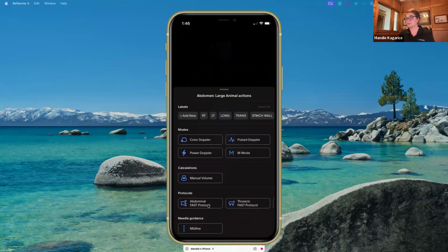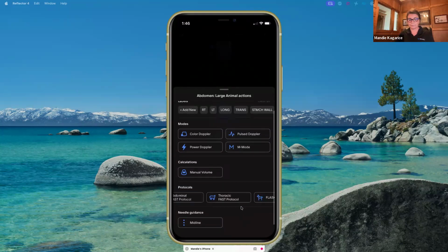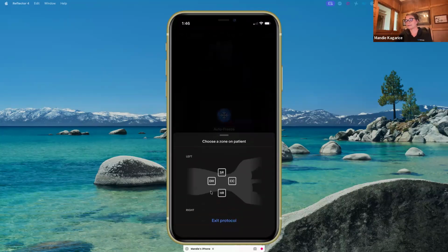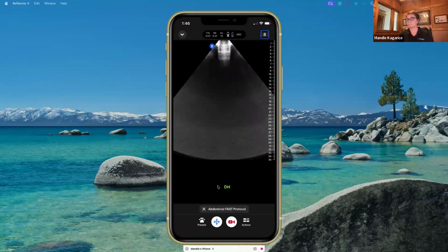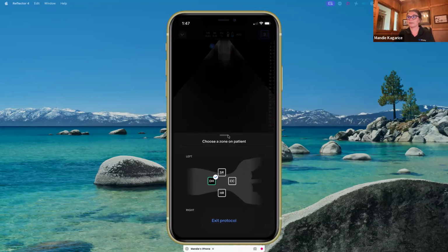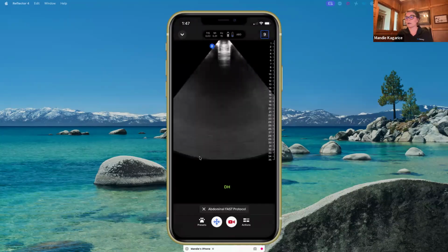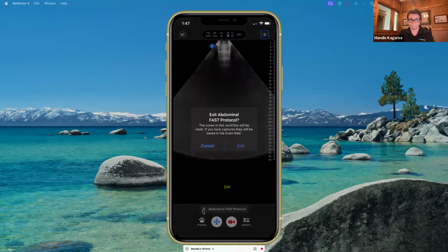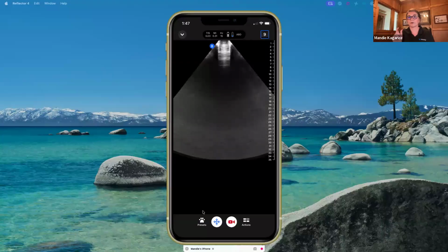You also have FAST protocols built in. If you're an equine practitioner, there is a colic flash protocol. I am going to tap into the abdominal FAST and show you how this functions. It will pull up those 4 quadrants. As you click a quadrant, it will bring you into your screen, pre-label that image for you so that all you have to do is freeze, capture, and unfreeze. And it's going to check that box for that specific quadrant as you work through that AFAST. Your thoracic FAST scan also gives you the same 3 quadrants that are a part of a thoracic FAST scan. And it will store those protocol images together within your gallery.